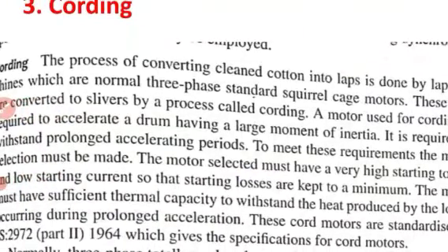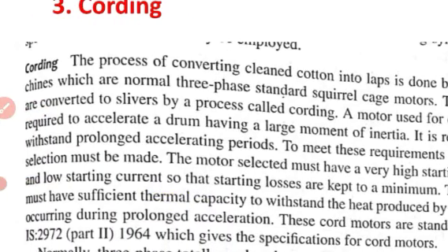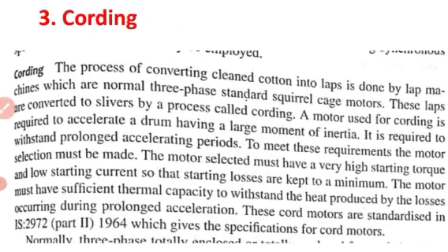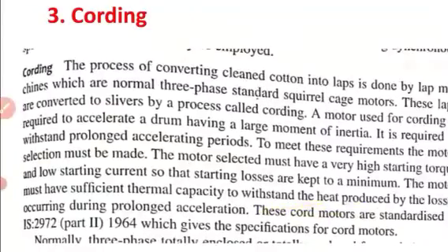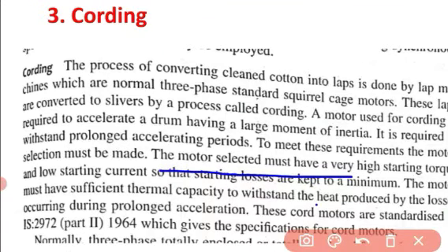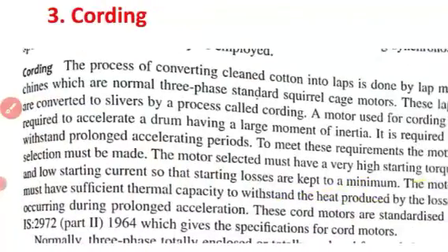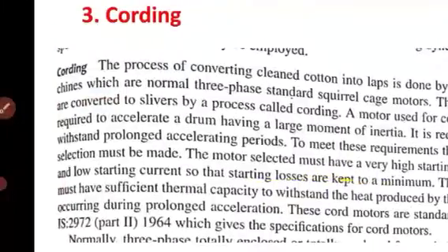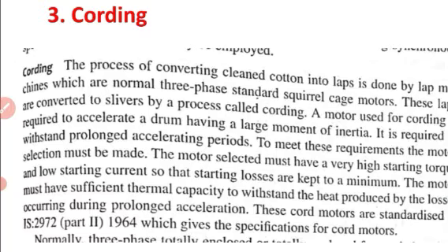So a drum with a large moment of inertia needs to be accelerated. For this purpose, the motor selected must have a very high starting torque due to the large moment of inertia, and sufficient thermal capacity to withstand the heat produced by the losses during prolonged acceleration, because it takes more time to start.